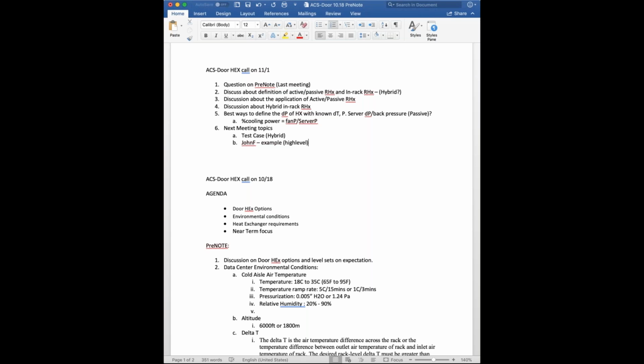No, agreed. A rear door is basically what we call a low velocity cooler. So you try to get the approach as low as possible, but there's always a balance because the back door is only a certain amount of square feet and it's not bigger than that. So at the end of the day, the amount of air running through it will determine what the approach will be. And to be honest, if we're looking at high temperatures within the hot area of the rack and the chilled water, it isn't so significantly a problem if the approach is 4 degrees or 6 degrees or 8 degrees. It really doesn't matter that much.